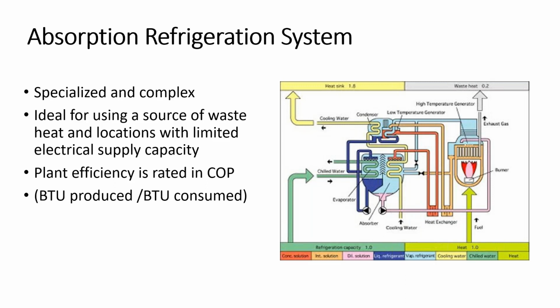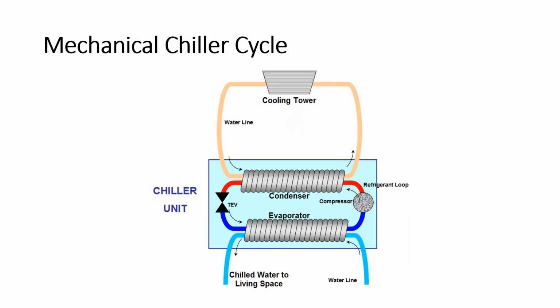But yes, if you operate them over a certain amount of time and you don't take care of them, they will solidify into a brick. They will get to the point that they will not do anything, and you just ruin the machine. So we're going to talk mostly about the mechanical chiller cycle. This is a blow up of the previous slide. On the bottom half is the chilled water side, the low side. That's the part that you're going to use the chilled water for. You transfer the heat out of the water into the refrigerant. The compressor picks up the gas refrigerant and compresses it to the high side, where it condenses back into a liquid. It's condensed because of the condenser water that you use to reject the heat, either to a cooling tower or a reservoir, or in the case of air cooled, it's just the ambient air. Okay, so this is just a simple cycle.